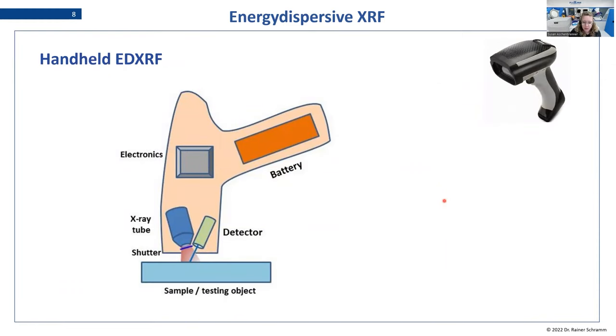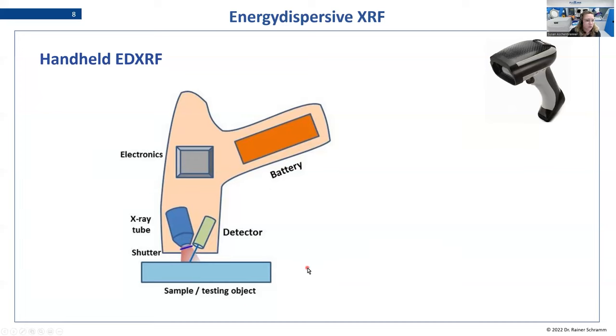A very nice option for EDXRF devices is a handheld option. It looks a bit like a gun with a battery in the handle, electronics, a small X-ray tube, and a very small detector. You can directly point it onto the sample or testing object. This is very good when you have testing objects that are very large and cannot fit into a sample holder, or if you need to measure on site and cannot move the sample. For these kinds of applications, handheld EDXRF is used.